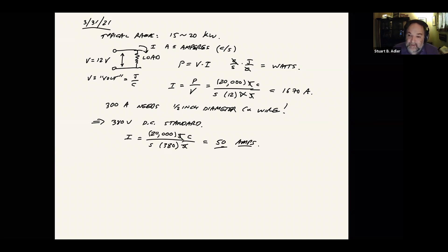And so that's typically what we would be trying to target. We'd have a fuel cell system, as we'll talk about in a bit, that means usually not one cell. We're not going to use one cell. We're going to use a stack just like, when you're in electronic devices, typically you don't have one triple A battery. You have two of them on top of each other or four of them in series to produce enough voltage to drive electronics. It's kind of the same idea. You would have fuel cells, but there'd be a whole stack of them. That's what a stack refers to: this stacking of putting fuel cells electrically in series in order to be able to add up the voltage. You have one volt, you have a cell operating at one volt, yet another cell operating at a volt and another cell operating at one volt. The volts are additive as you stack them up. And so we'd be looking at some stack of cells that would be enough to bring the voltage up to 380 volts and thus be compatible with the electronics control systems that would be in our data center.